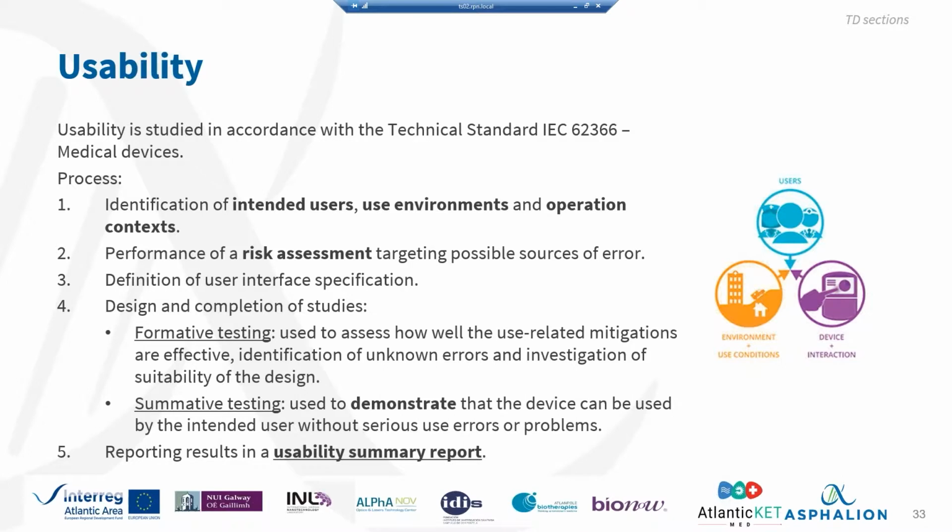Where is a device going to be used? Is it going to be used in a hospital? Is it going to be used in a particular clinic? Is it going to be used in a house? It's quite important to define these matters so as to be able to assess if the device is used properly or not.